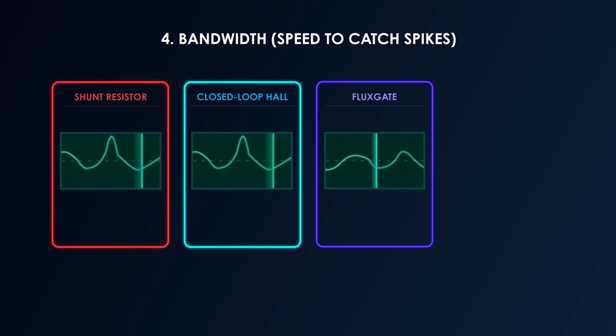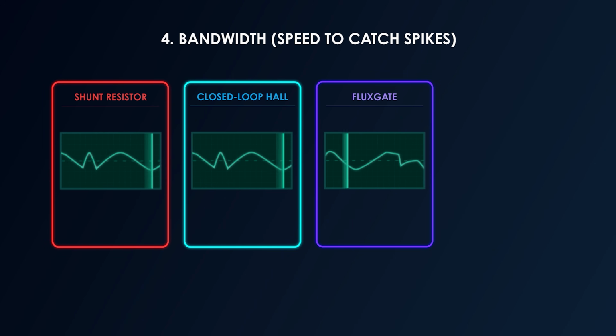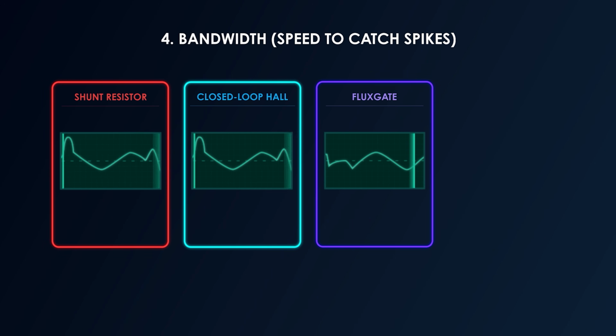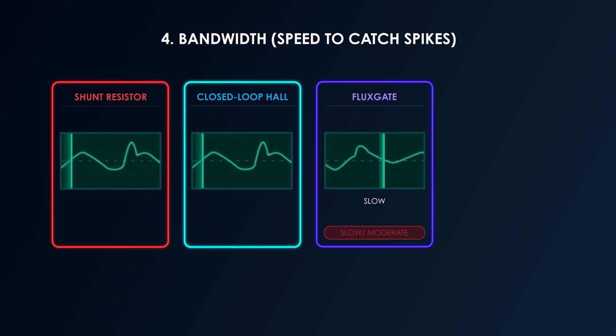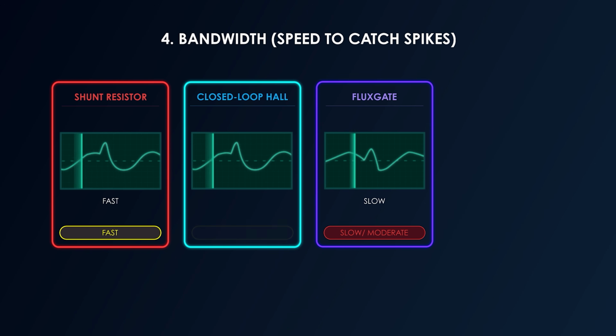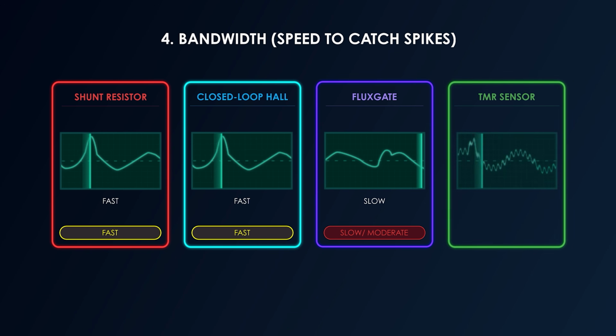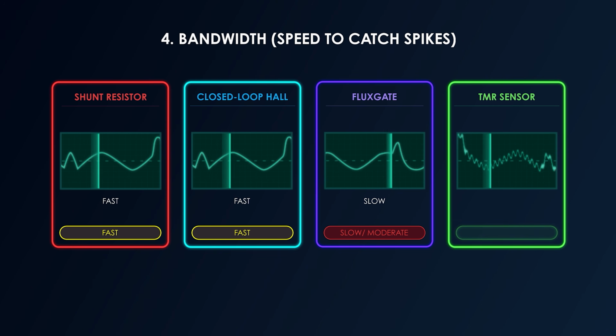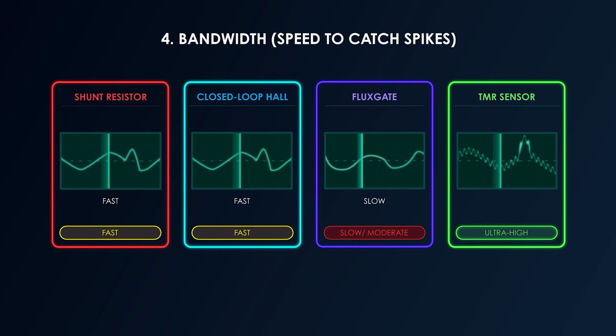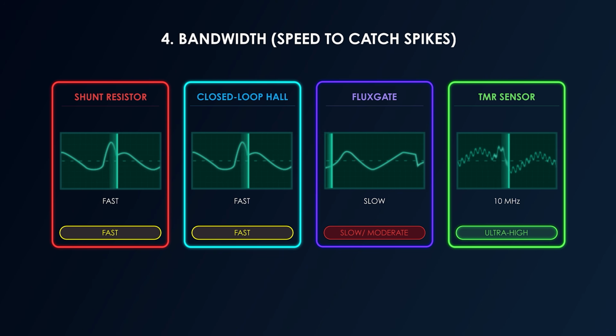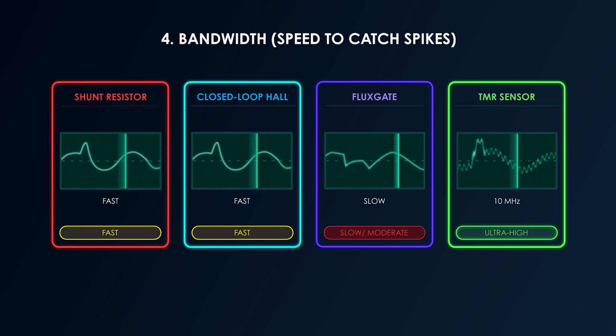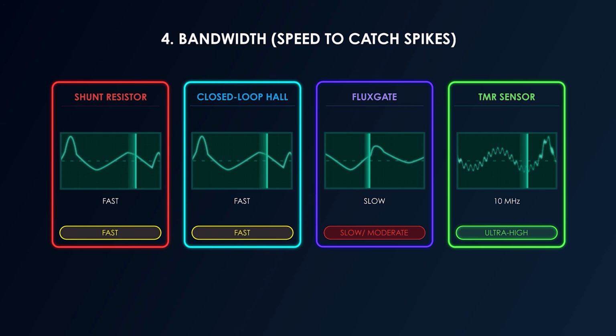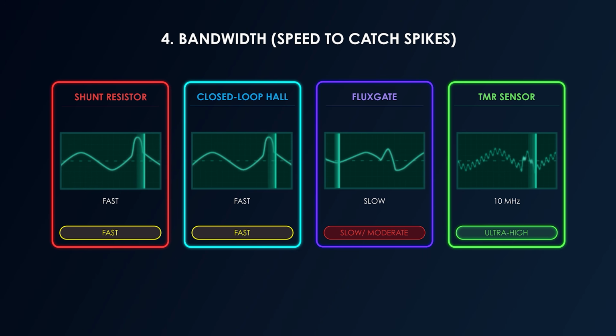Fourth is bandwidth. If you are using those fast silicon carbide inverters, we need a sensor that can keep up. The shunt and Hall are fast, but the TMR is the fastest. We are talking ultra high bandwidth up to 10 MHz, fast enough to see electrical spikes that other sensors would totally miss.